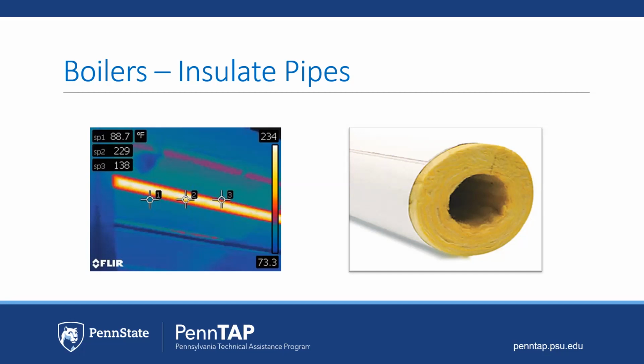PennTAP recently conducted an energy audit at a plant located in southeastern Pennsylvania. We took several images of the uninsulated pipes using an infrared camera. The infrared image shown here was taken at that site where approximately 221 feet of pipes were not insulated. 793 MMBTUs of heat was lost through bare pipes each year. Once the pipes were insulated, this client saved $3,795 on fuel oil annually and reduced heat loss to 114 MMBTUs. The simple payback period for this project was just over 1 month.